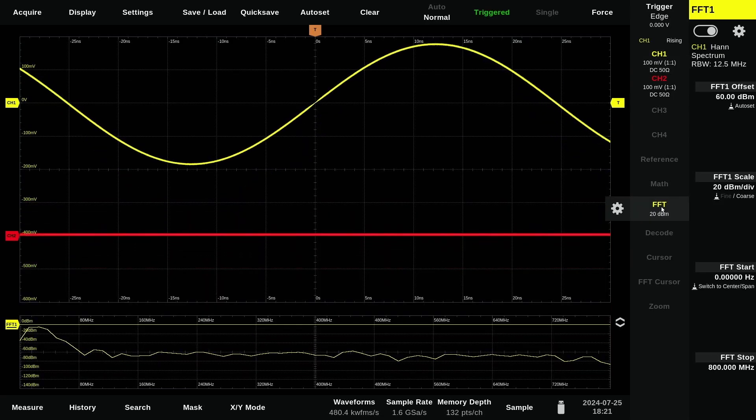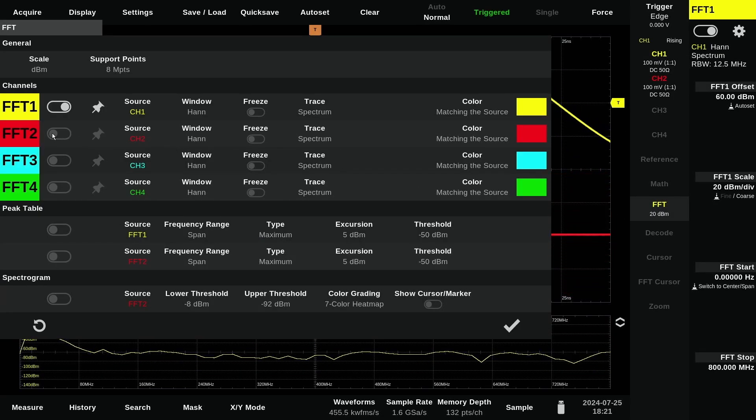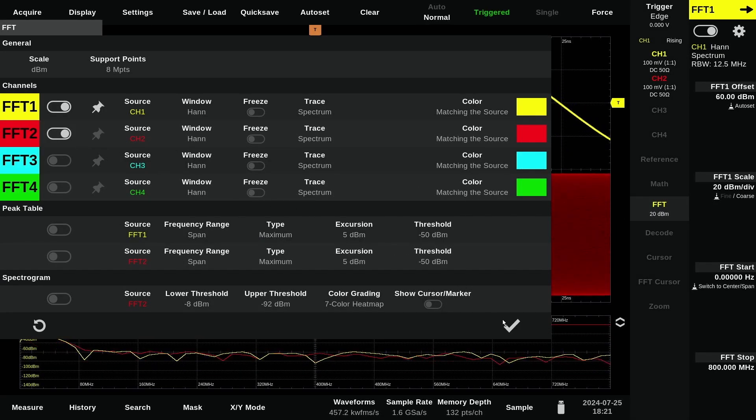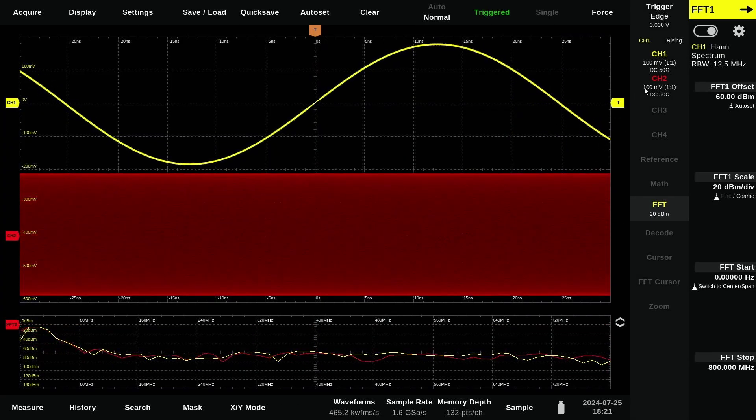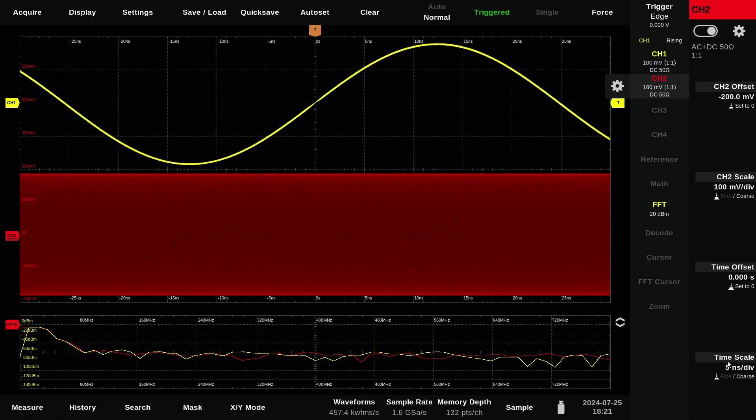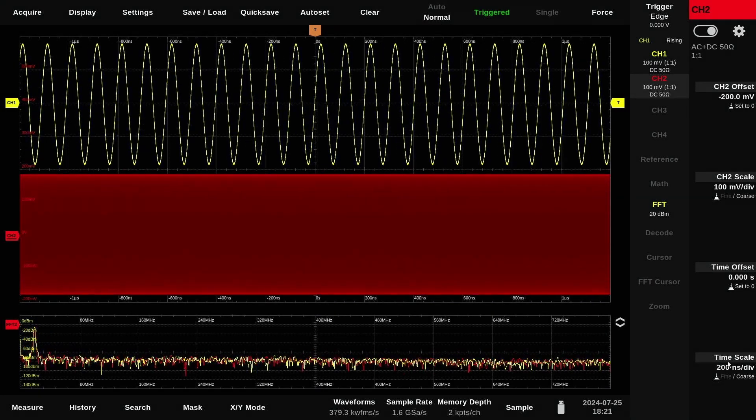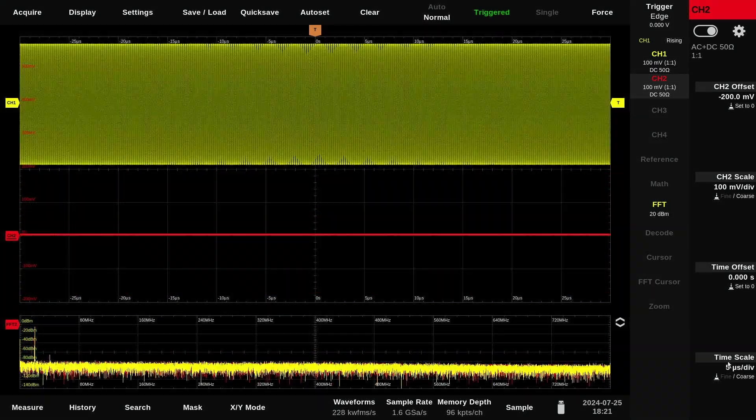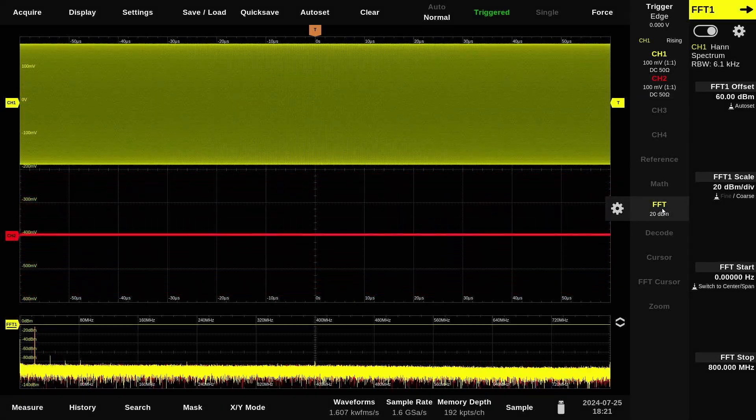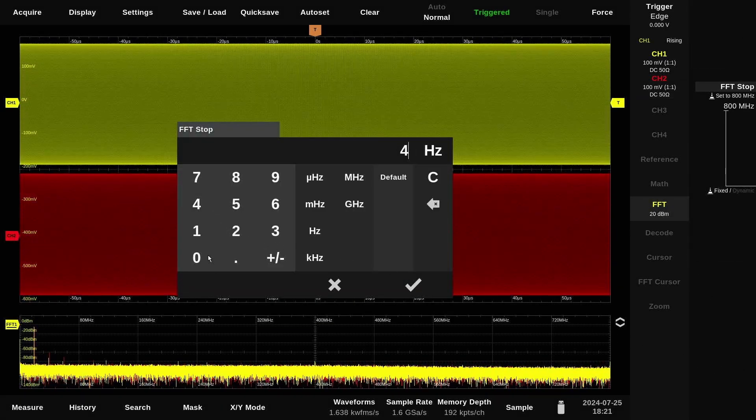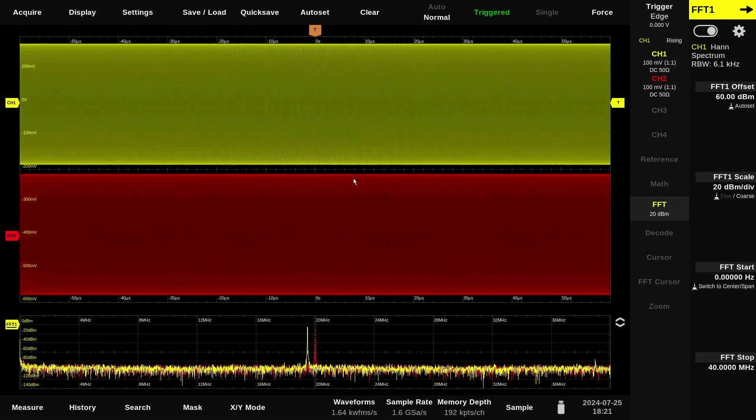Analyze noise, find the cause, check signal quality, and more. The FFT is one of the most important analysis tools of an oscilloscope. With up to four simultaneously running FFT channels, each with up to 8 million data points and many functions, the MagNova places a strong emphasis on a particularly powerful FFT.